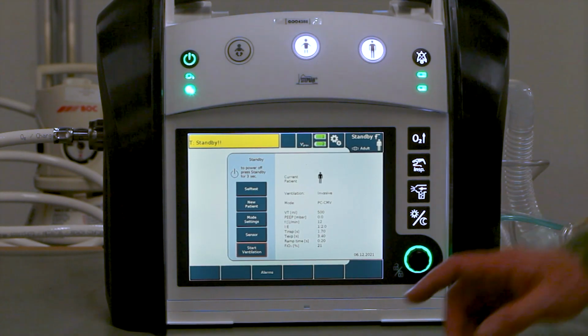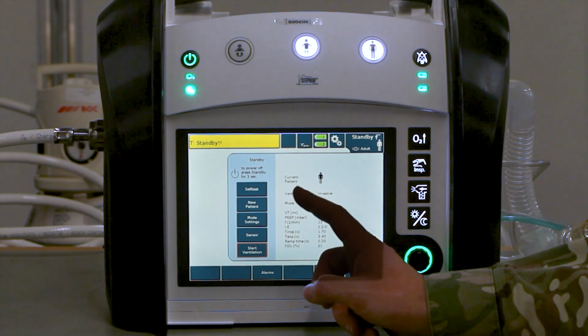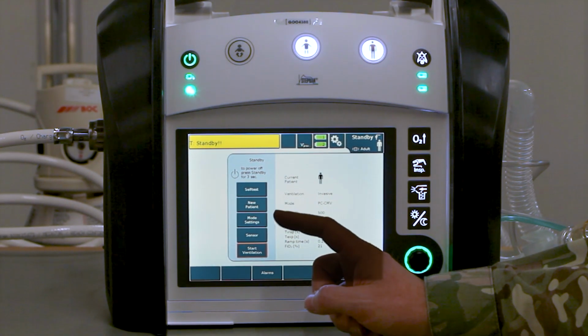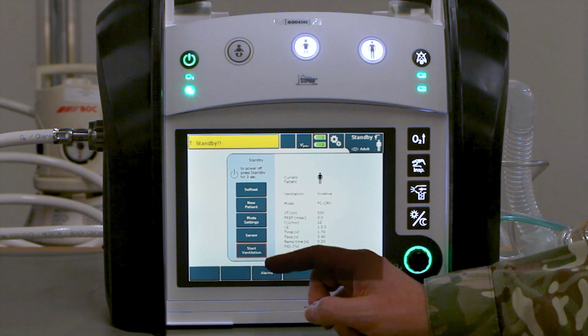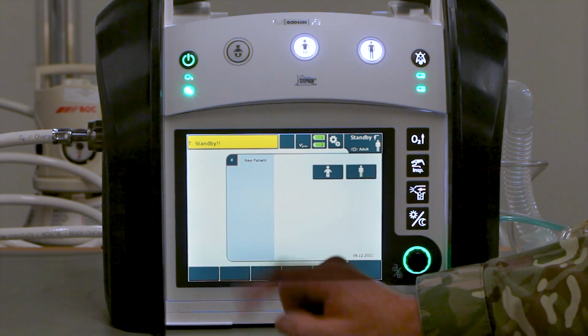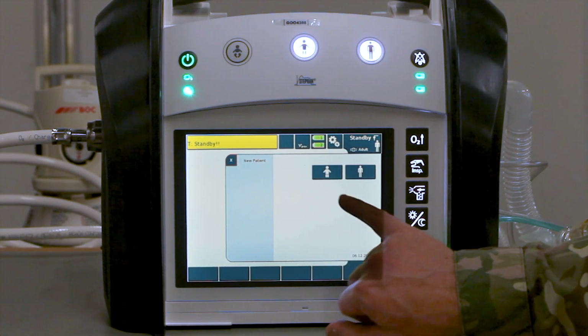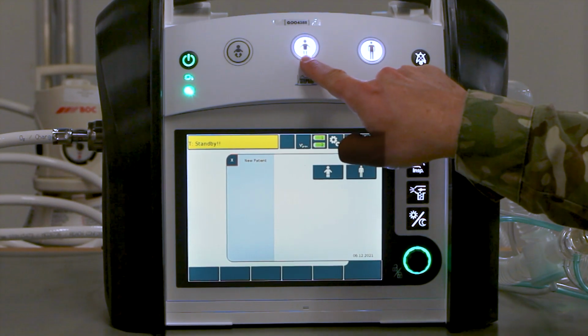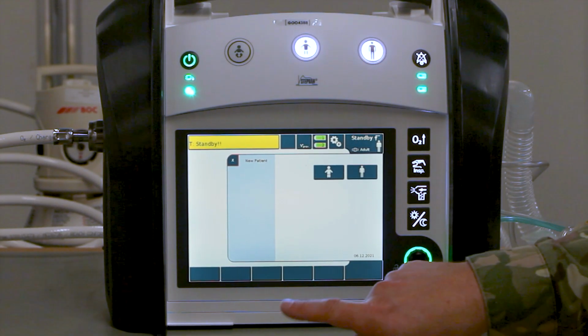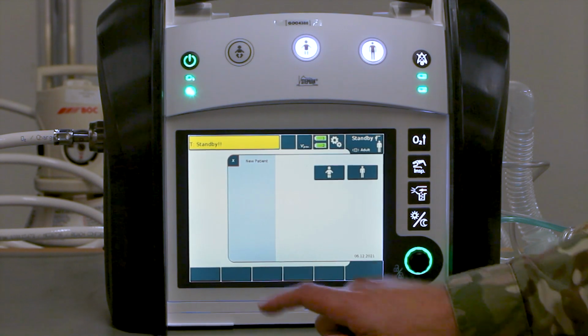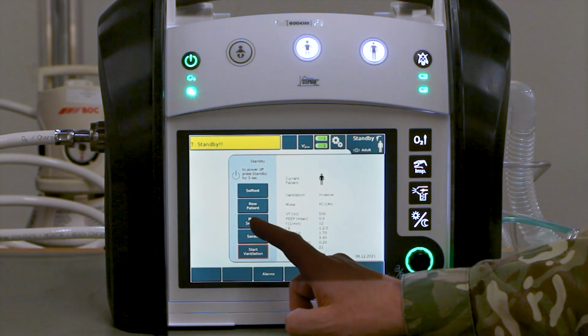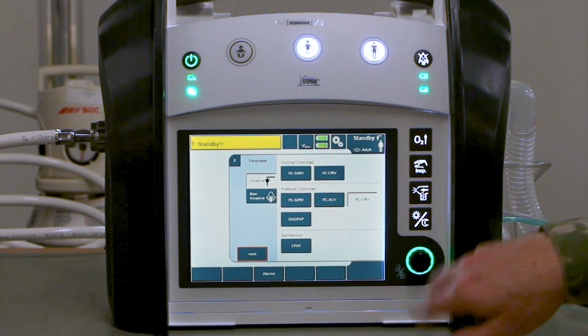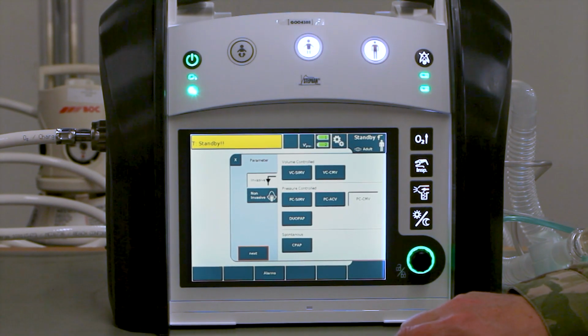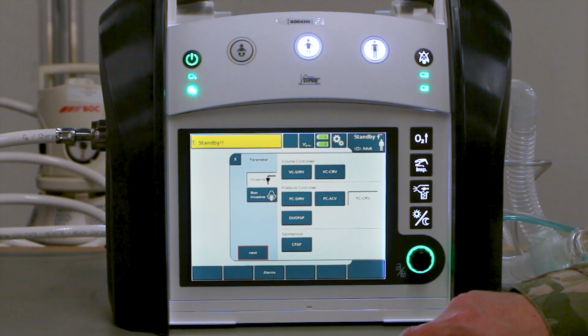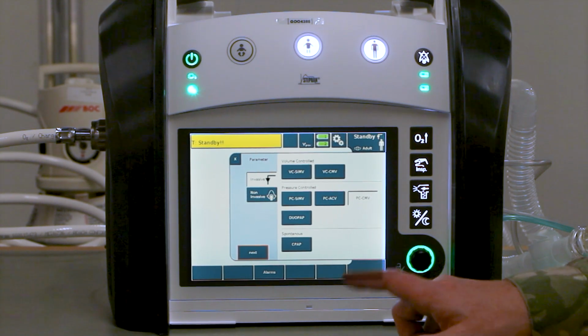The home screen will offer several different menus. First of all, you can repeat the self-test at any point if you change circuits, for example. You can click New Patient. This will give you the same options of starting a new patient as using the Quick Start buttons on the top, as previously stated what our default settings are. You can also click the mode settings, which will give you all the different ventilatory settings, whether it be invasive or non-invasive, and that could be then preset and confirmed and set in the background.